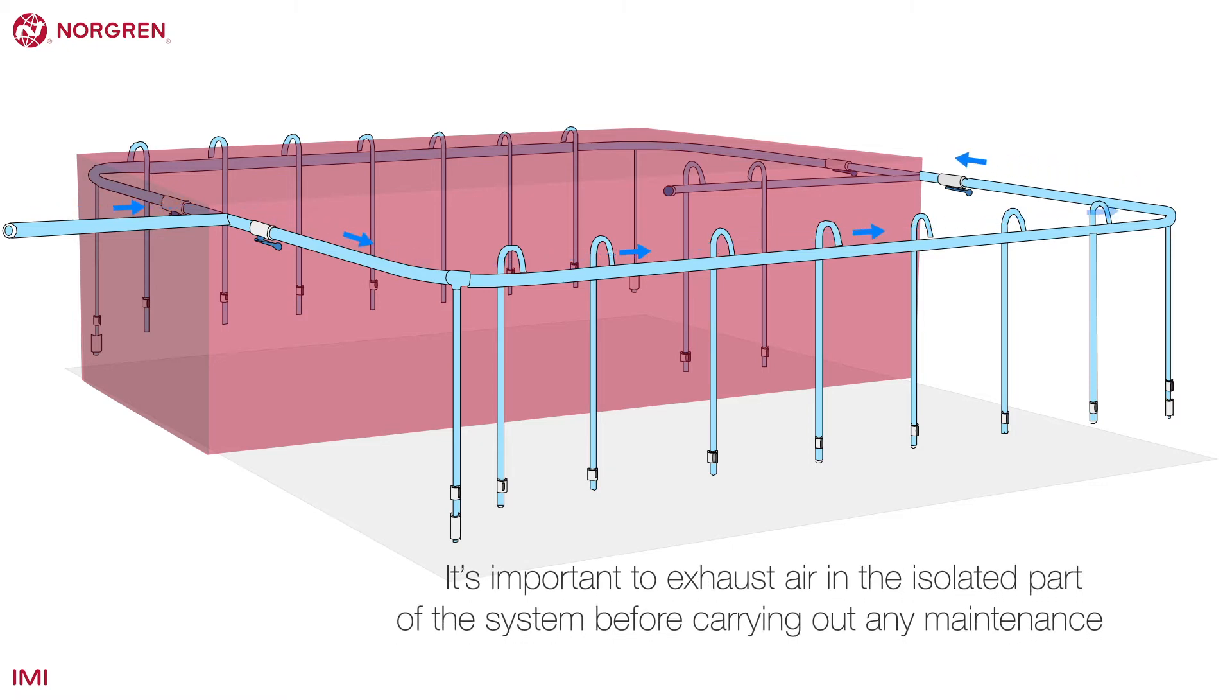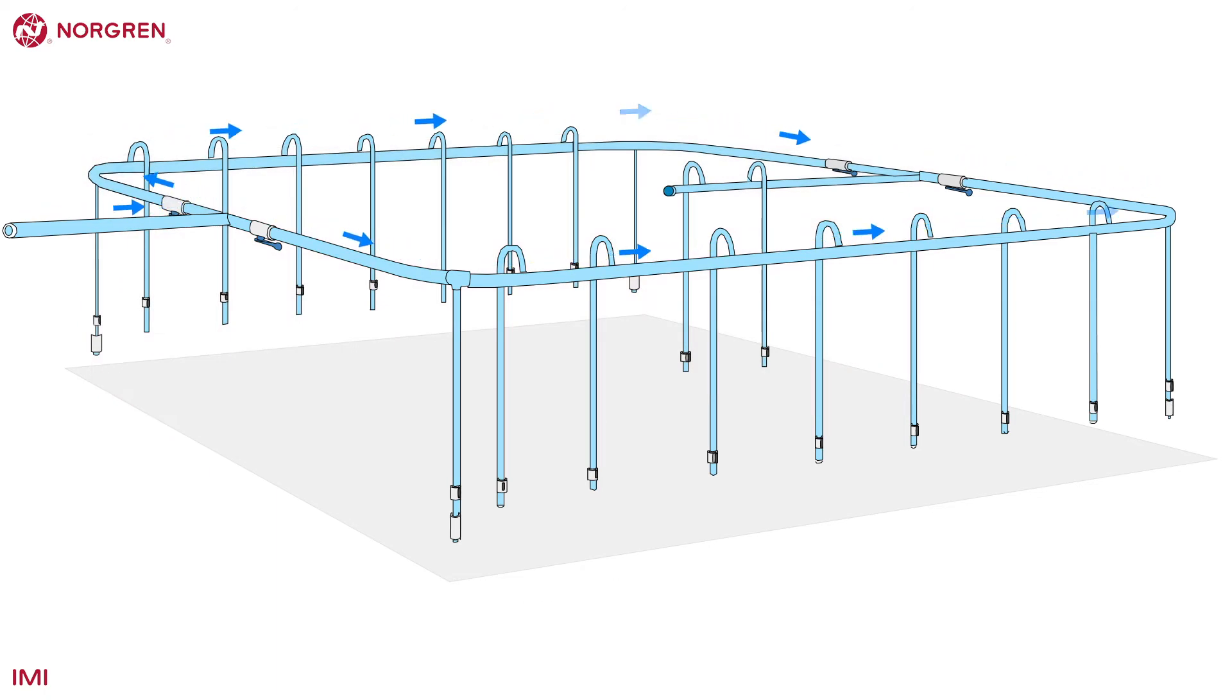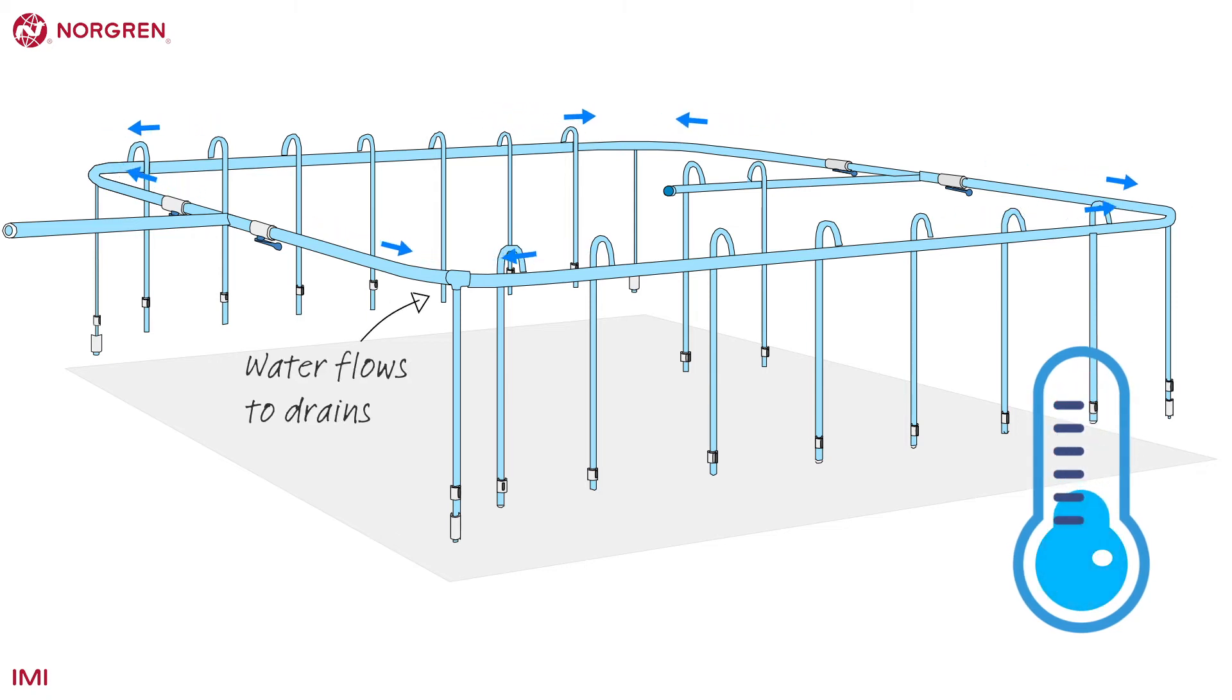It's important to exhaust air in the isolated part of the system before carrying out any maintenance. The ring main will slope to the corner, allowing any water that forms should the temperature drop to flow toward the drains.